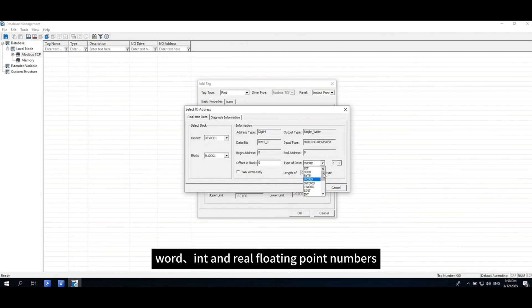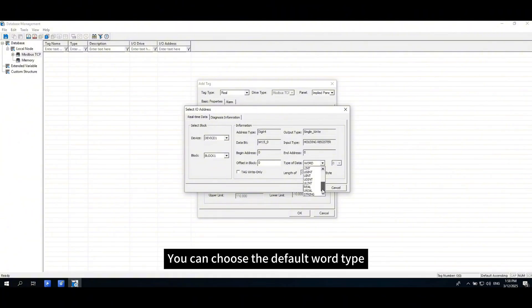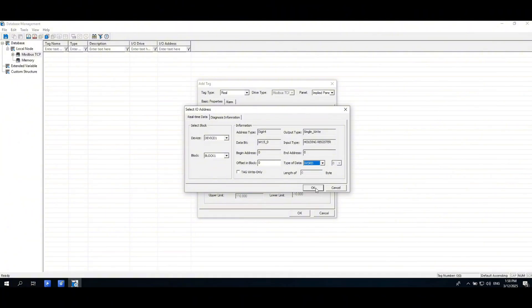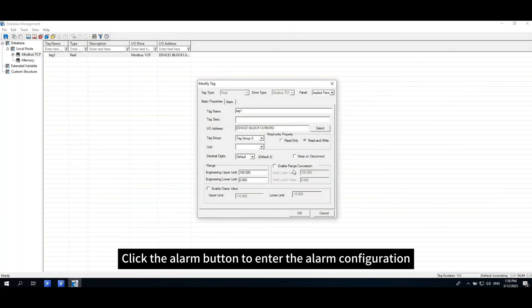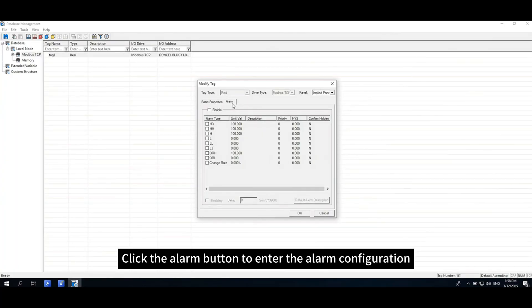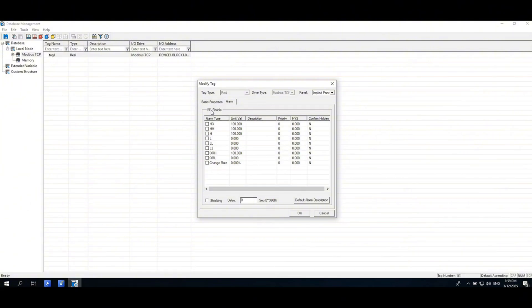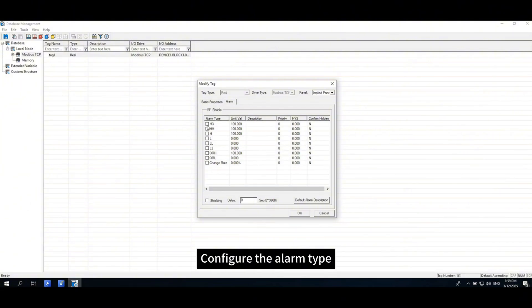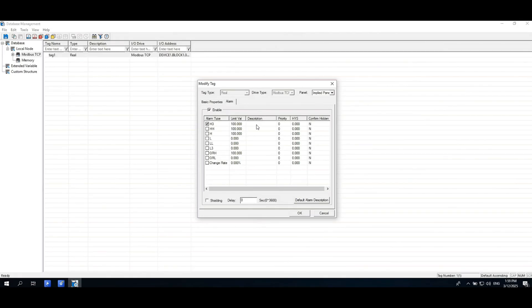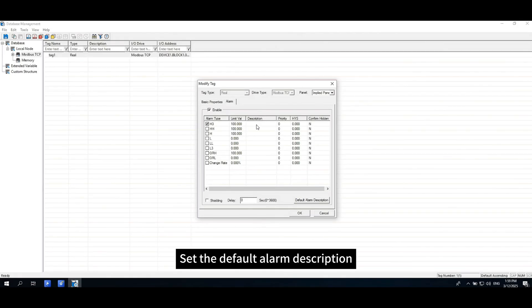Supports bit, bool, word, int, and real floating point numbers. You can choose the default word type. Click the alarm button to enter the alarm configuration. Select whether the current tag is enabled for alarms, configure the alarm type, set alarm types and limits, and set the default alarm description.